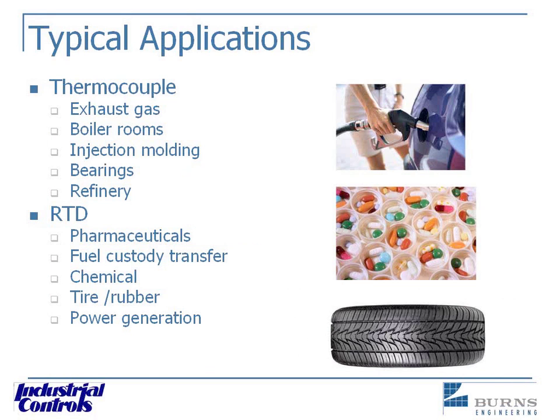And I don't know, Harold, do you have anything to add here? Maybe talk about the... Yeah, in fact, I do. I was thinking, these different applications, you think of the standard, maybe a direct immersion into a process with a temperature probe or a thermowell, but you may have a need for a non-intrusive application where you can't have anything touching the process. Well, we can do that. You may have a need for a sanitary tri-clamp type application. Well, we can do that too. You may have a need for a temperature sensor, but it's just not giving you enough room to actually stick a probe down into a process. Well, we've got something to do that as well. So if you have an application out there that you think may be a little difficult, run it by us. Let us take a look at it. It may surprise you what we have in our bag of tricks.